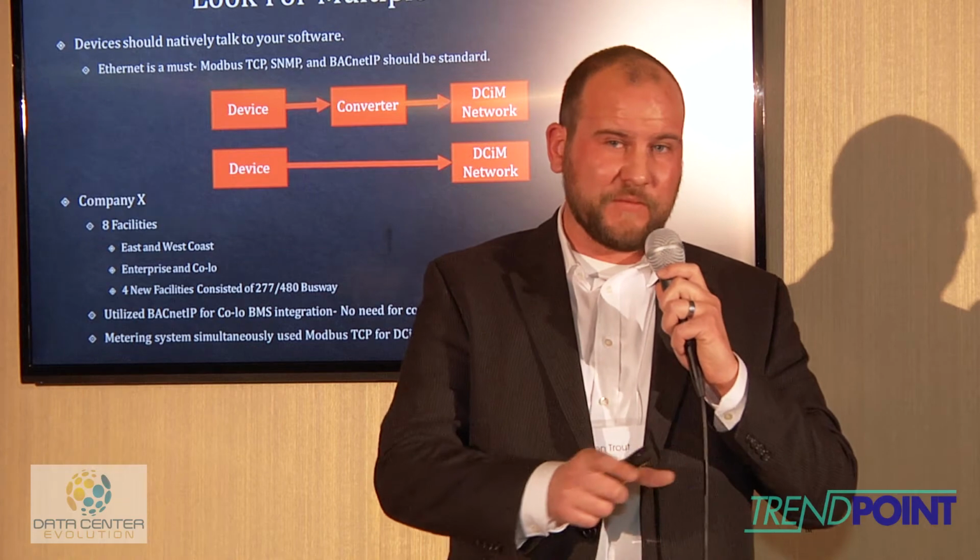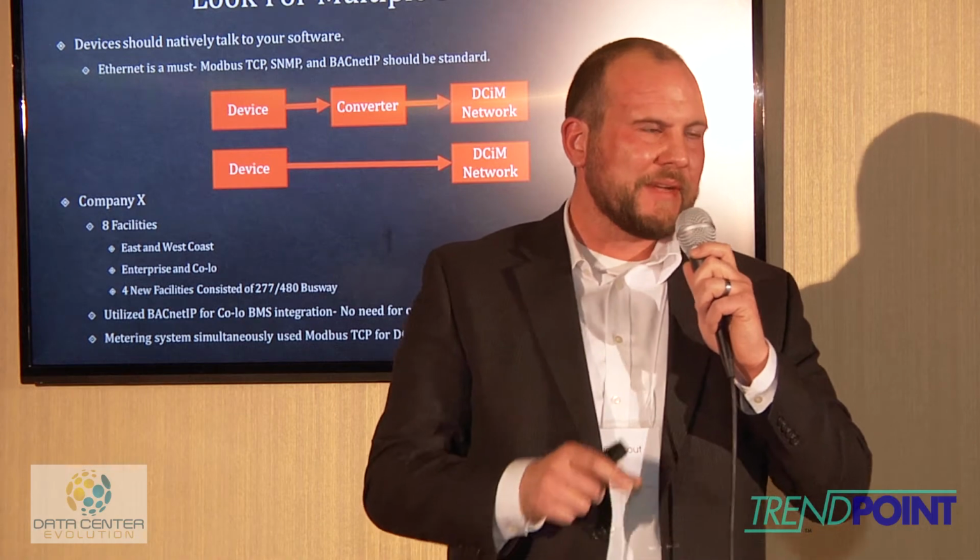And so they wanted a device that was flexible enough, was their first criteria. They've got a lot of busway, 277, 480 busway, they have some existing PDUs. But the second thing is it had to talk to Allerton, and the same device had to be ready to pull into their DCIM initiative that they're rolling out over the next 12 months. So they chose a device that could work today and could work 12 months from now because of the protocol flexibility. No hardware changes had to be made for them to switch from BACnet to Modbus to SNMP, depending on which software they wanted to pull that into and which way they wanted the DCIM. So their DCIM decision wasn't limited by the devices they selected.